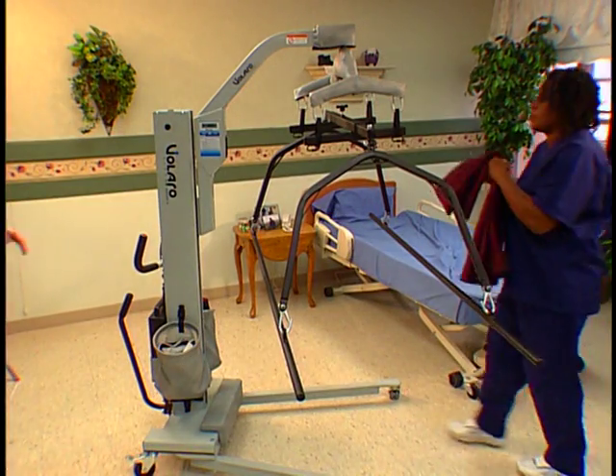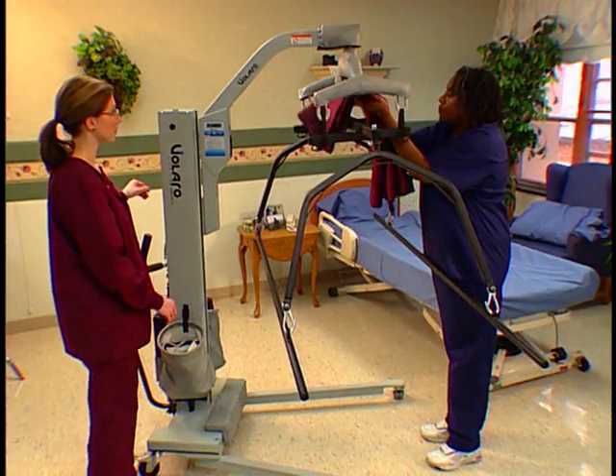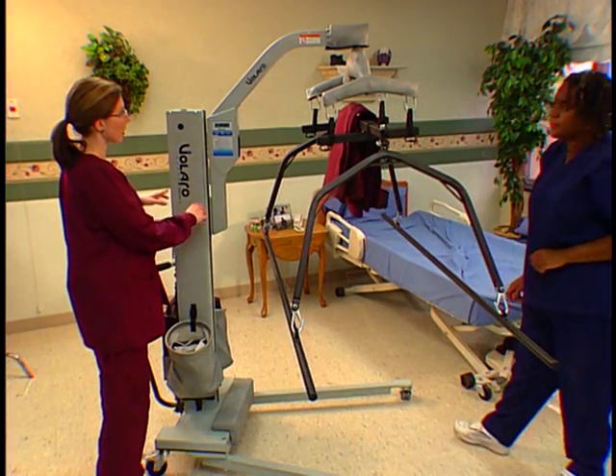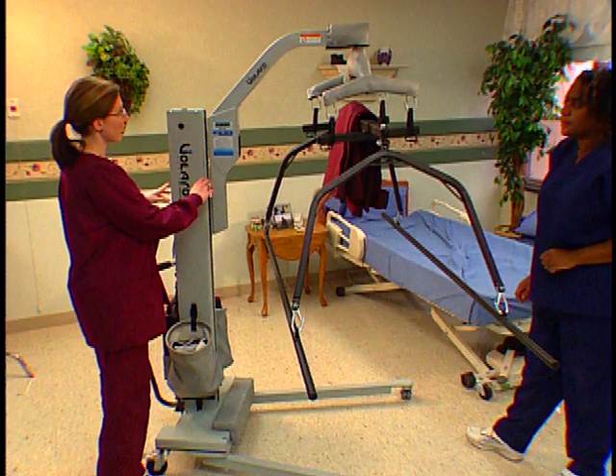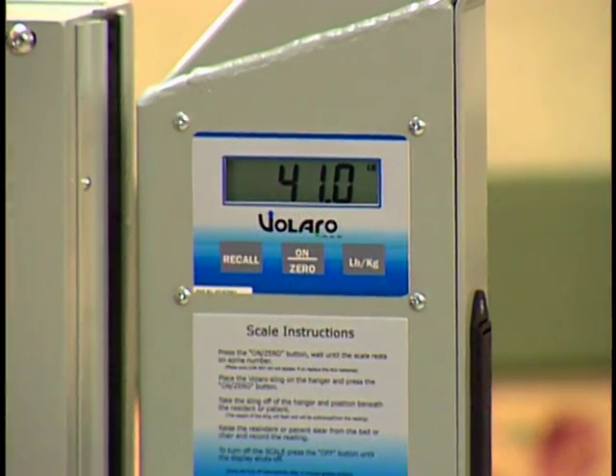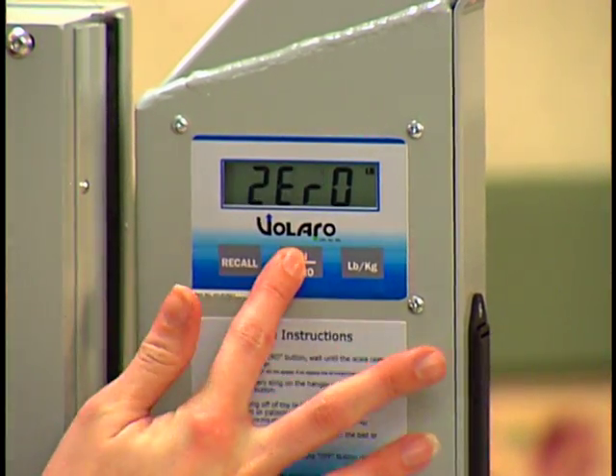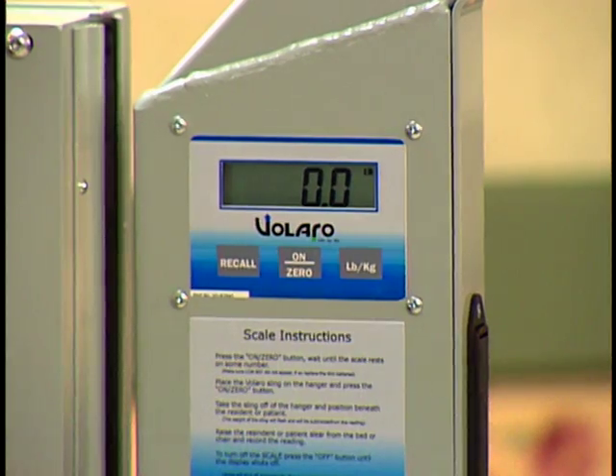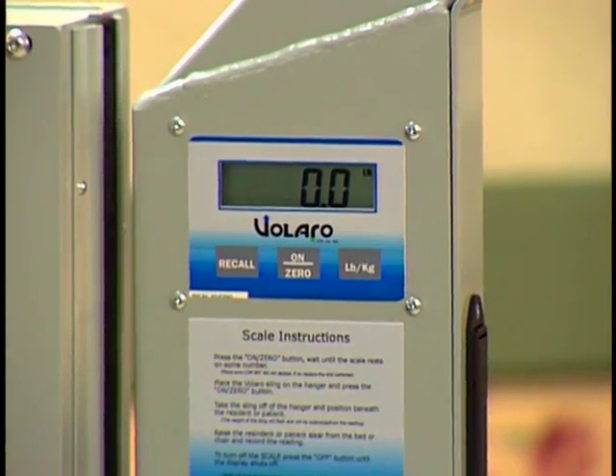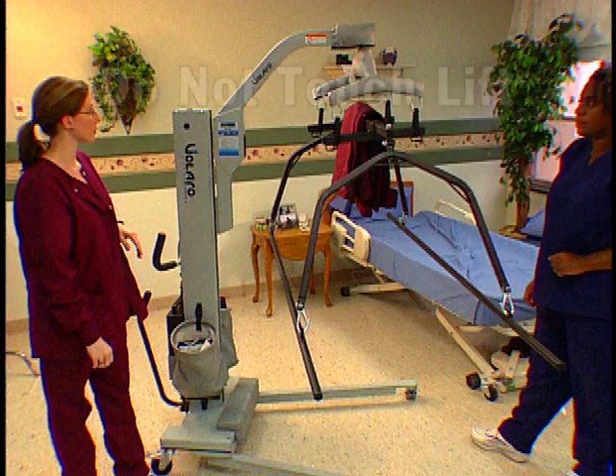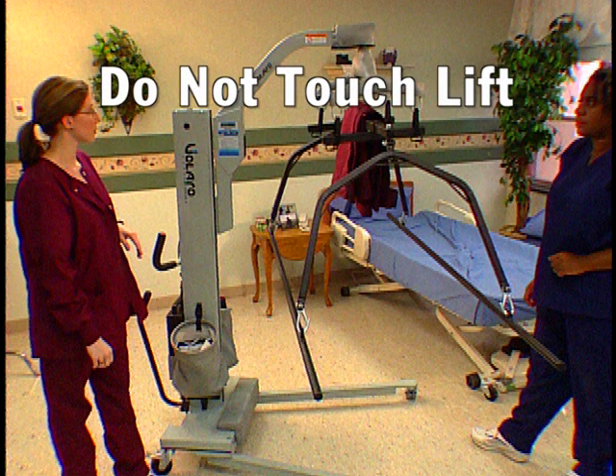Suspend the sling and accessories from the hanger bar with the 4 hooks, making sure they do not come in contact with any other part of the lift or the floor. With the scale on, press and release the On Zero button again. In a few seconds, 0.0 will appear on the display. It is important that you do not touch the lift during this countdown.